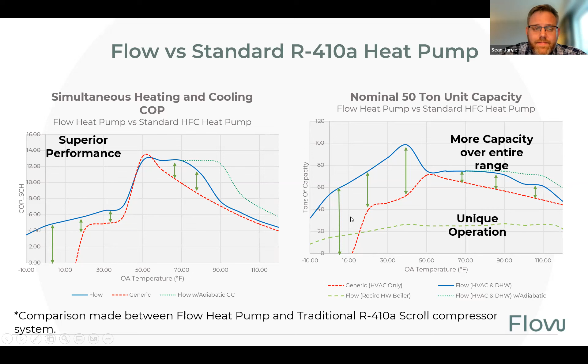The CO2 heat pump holds at or above the rating condition all throughout the application range, versus, you see how as you get hotter and as you get colder, the 410A heat pump just falls apart on overall capacity. And that's where you have to start injecting additional things, and why for anything below 20 degrees the recommendation is to use electric resistance heating or electric boiler backups. And that's really because the refrigerant has limitations there.